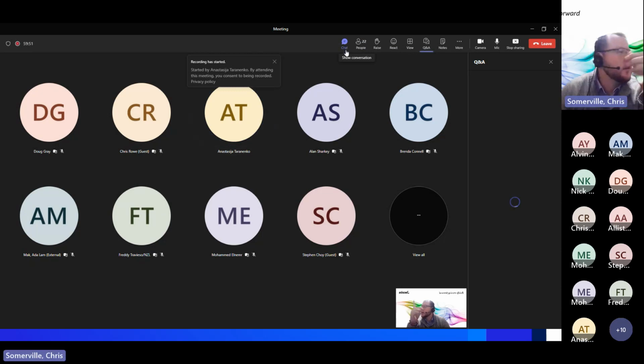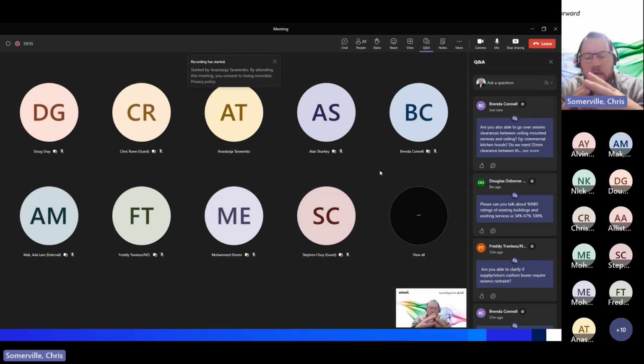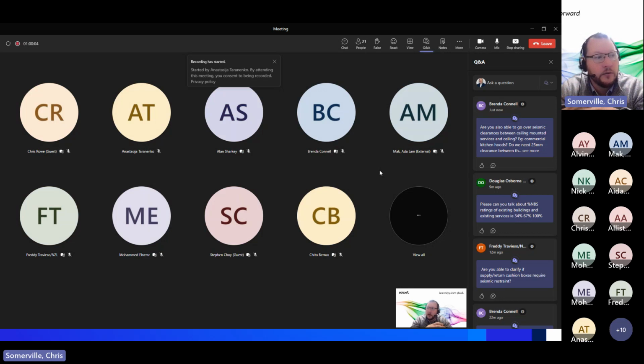I can see Chris raised one about the 7.5 and the 10 kg. So the 10 kg is from 1170.5 before the amendment, but in Amendment 1 they reduced that down to 7.5. So that's generally what I would advise we use, although it's not cited, so legally you don't have to. I hope that answers the question.